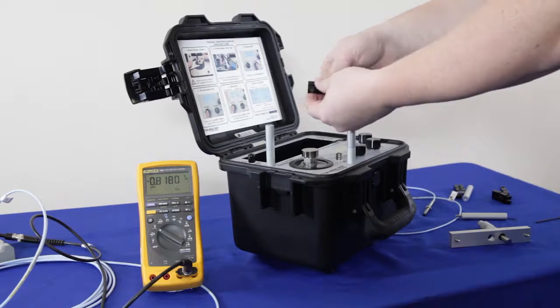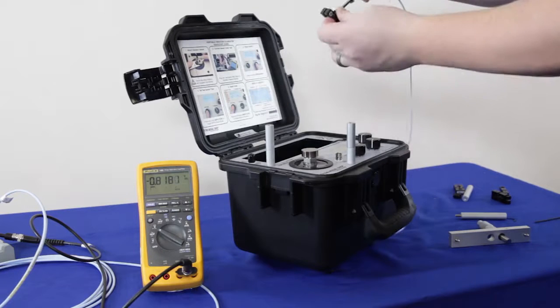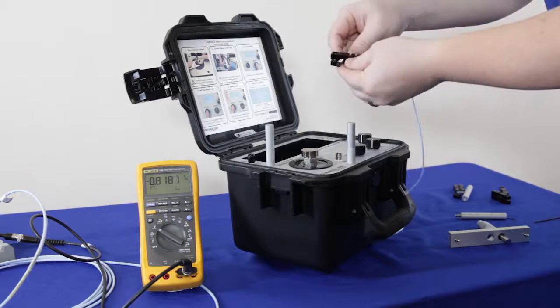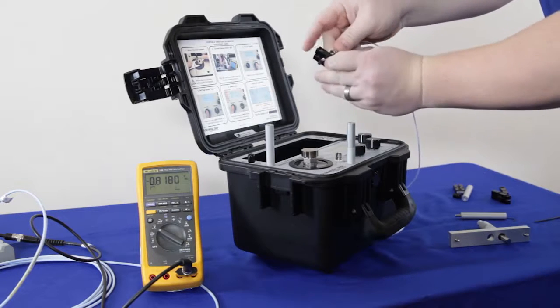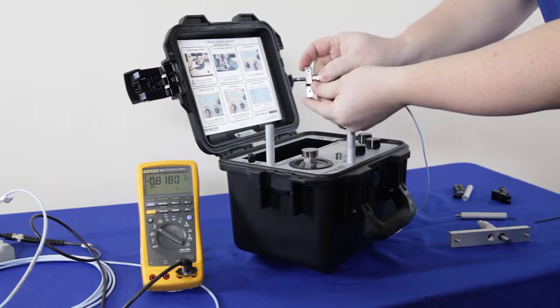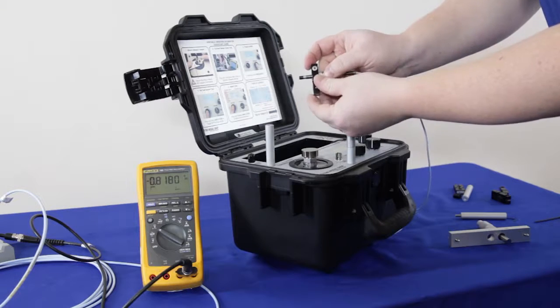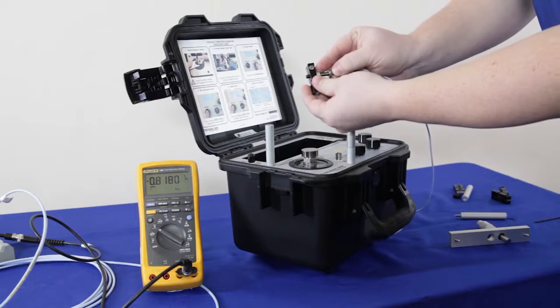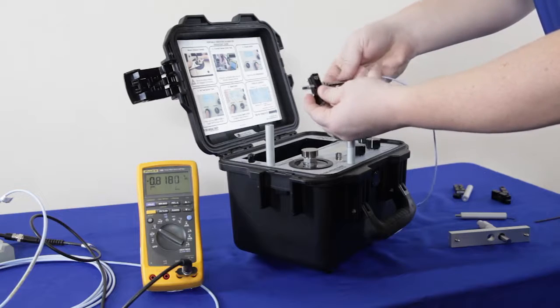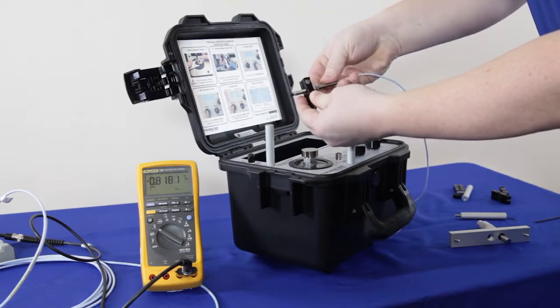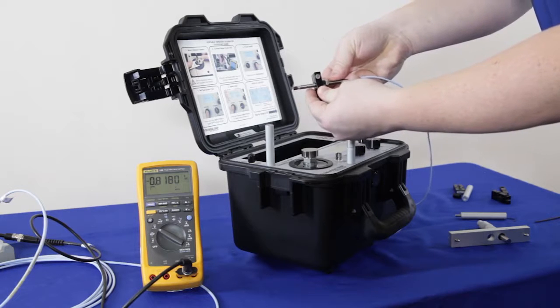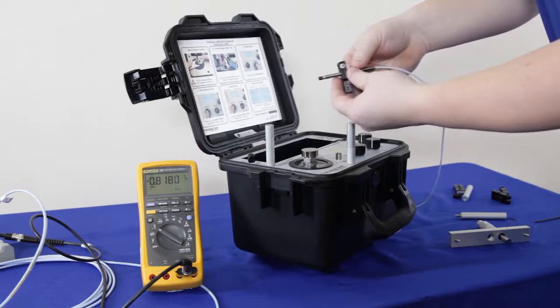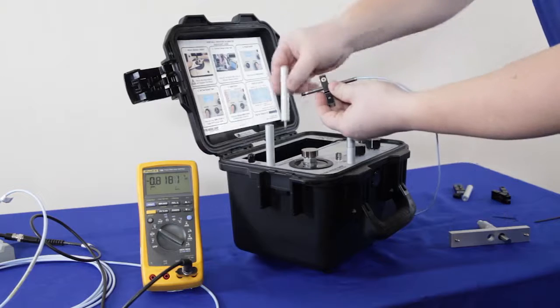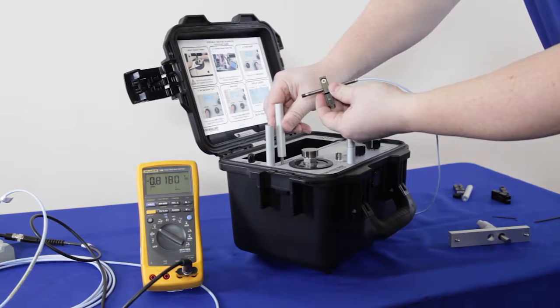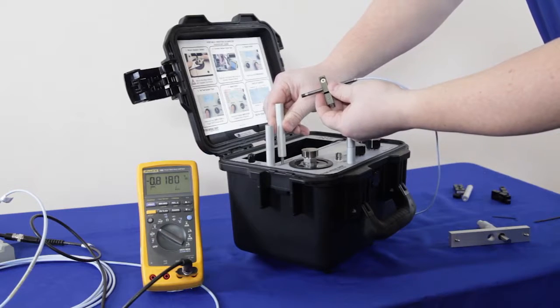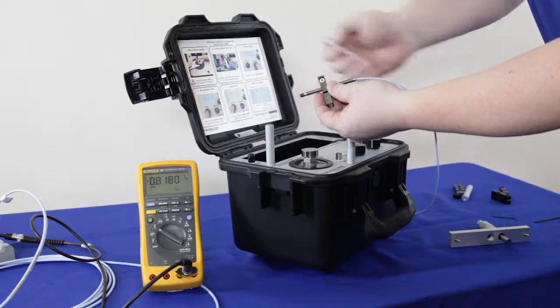So one thing people always ask is, how much of my probe should be sticking out the bottom of the black bracket? Well, I like to have about 1/4 inch of the probe sticking out the bottom of the bracket, but if you mount it here, not a big deal. If you have even more sticking out, if you mount it this far down or even further, it's not going to affect your test. In that case, I would just need to use a longer standoff for my probe bridge, and you'll see that in a moment, and we can compensate for that.